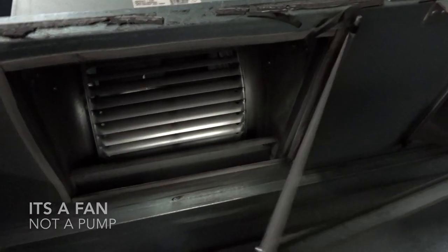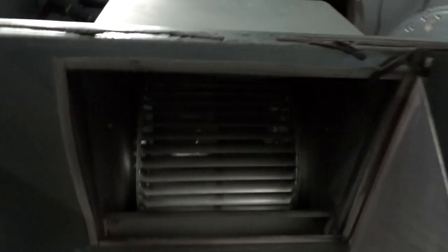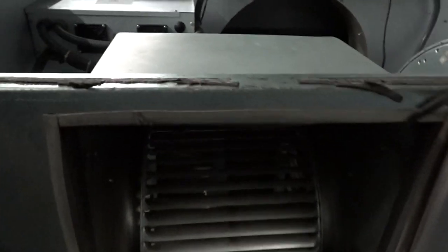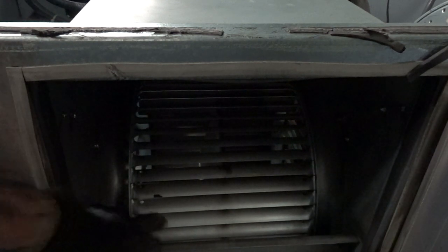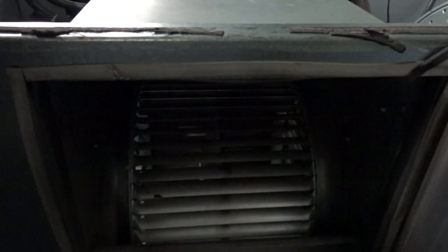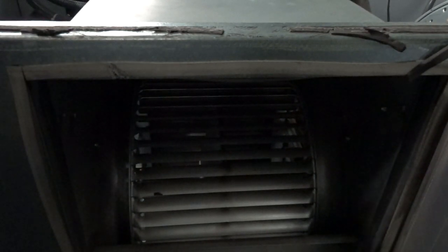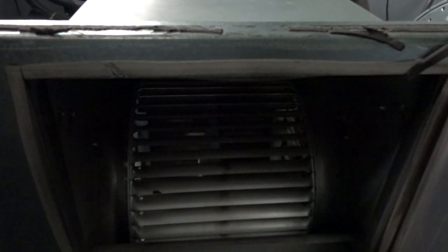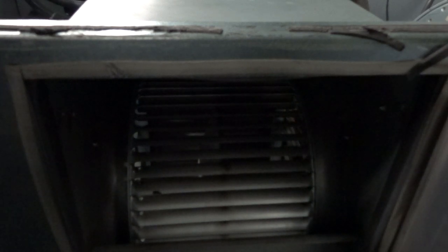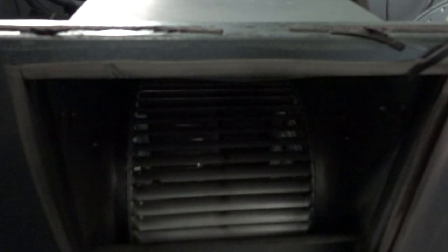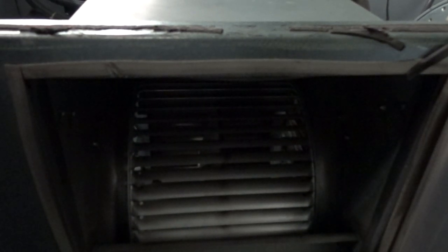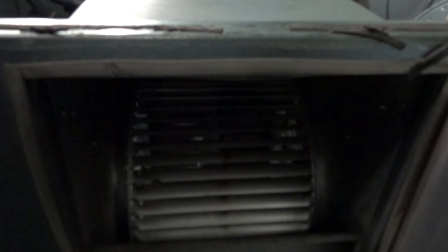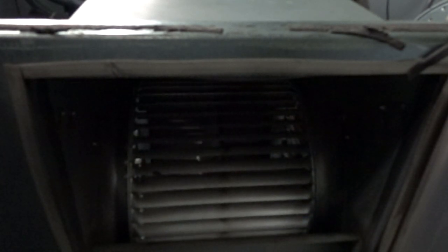I'm going to check the fan. On our fan we have a black mark which is just there, and I've put that there on my last maintenance visit to note when I've done one complete rotation of the fan. So what I'll do is I'll turn the fan in an anti-clockwise direction checking the fins for any cracks, burrs, tears, splits, or anything untoward.